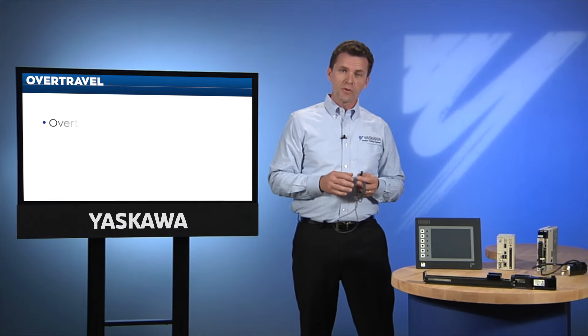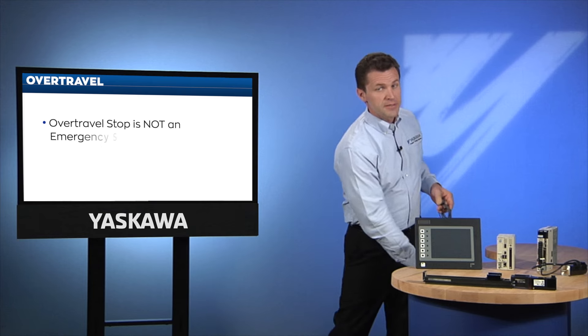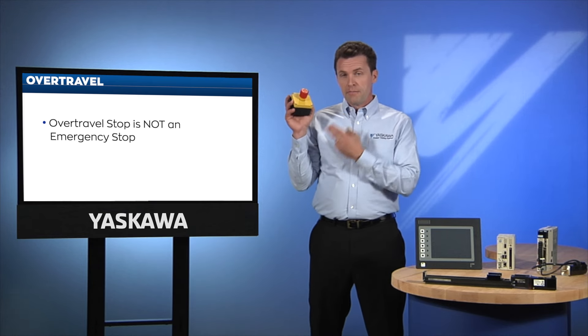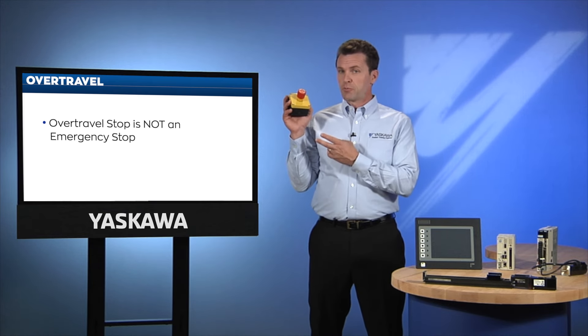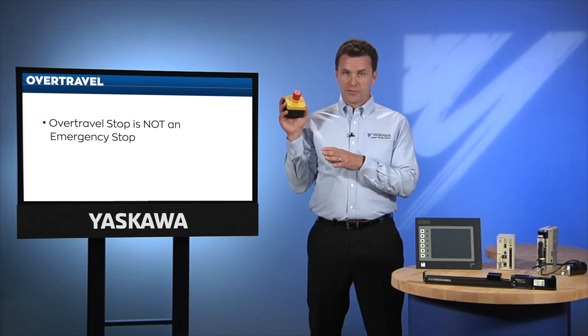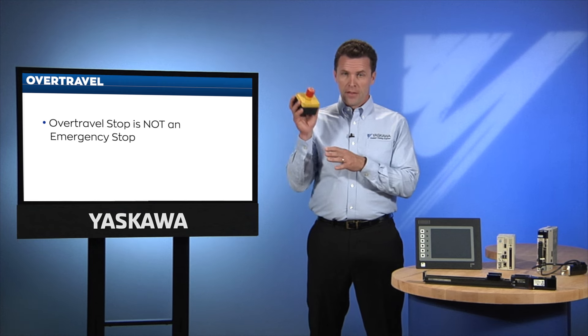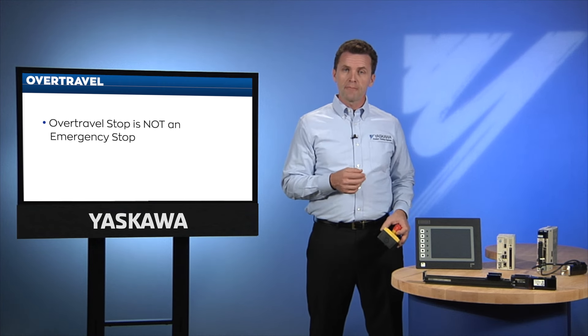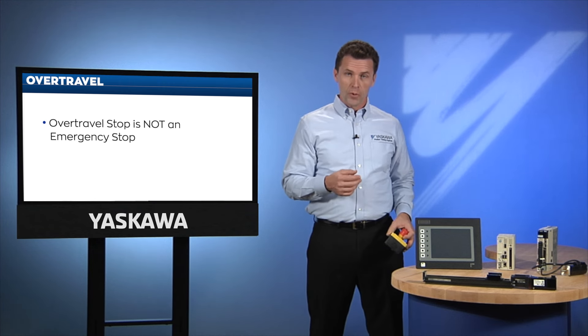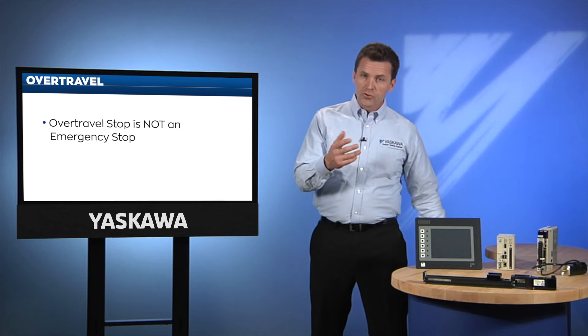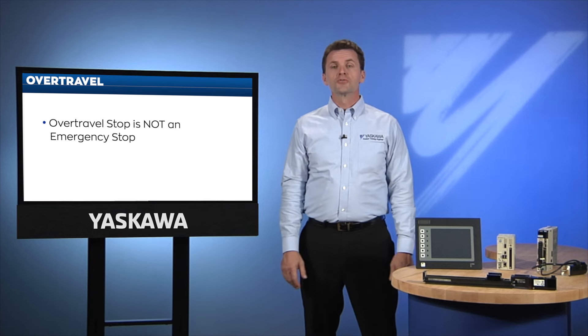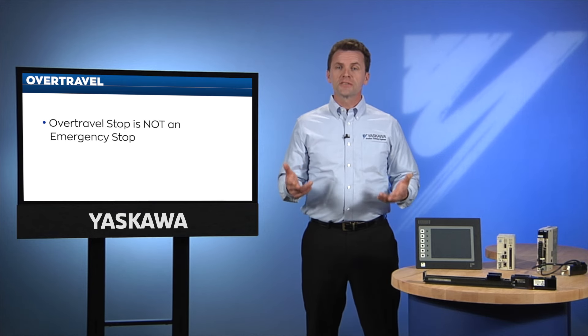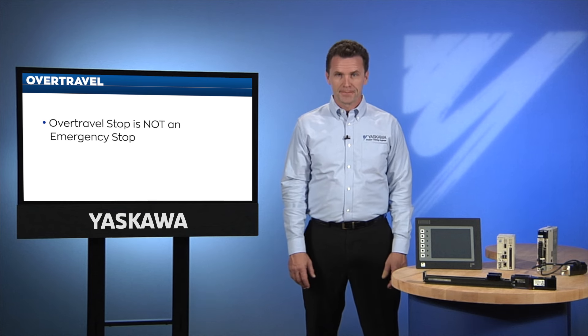It pays to remember that an over-travel stop is not an emergency stop. An emergency stop would prevent all motion in all directions. An over-travel stop is simply a quick way to stop motion in one direction. In an over-travel condition, the controller can be programmed to recover and the servo can still be moved in the opposite direction.